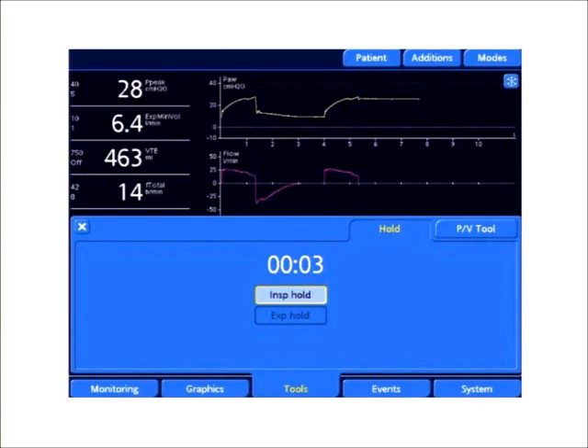The way to do this is to find a target P-High setting. Ideally, you want to do a plateau maneuver or measure a plateau pressure, and you do this by inspiratory hold maneuver.